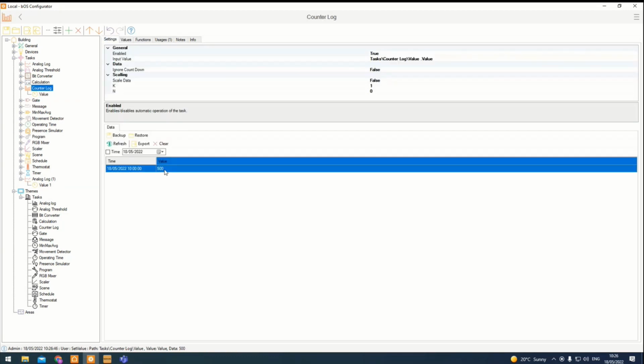The log is going to be saving this value by hour, basically. So we are looking at, let's say, consumption per hour, regarding any specific input device, and then each individual hour, the next value is going to be saved. So let's say currently this device is consuming 500, whichever unit you have, and then in the next hour it's going to consume 550, so it's going to consume 50 more, and the log is not going to save 550. It's only going to save 50, because it subtracts the previous value. I hope that makes sense.